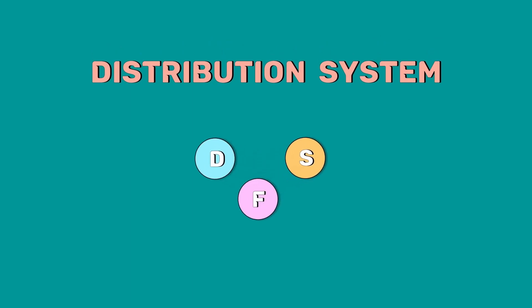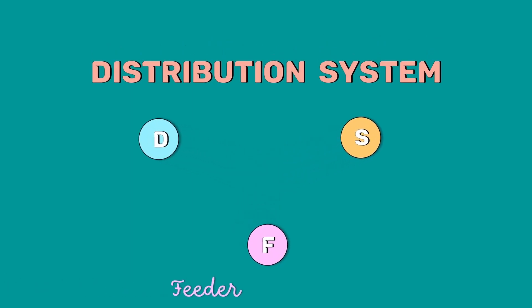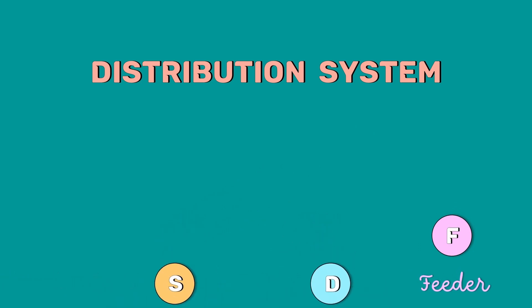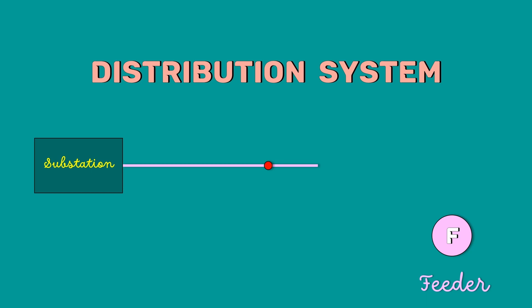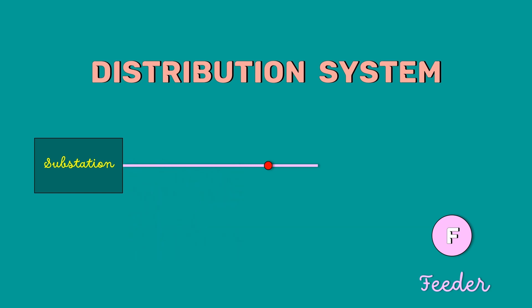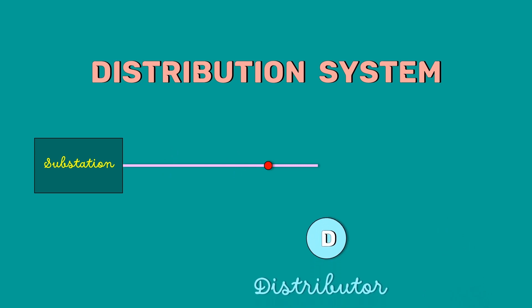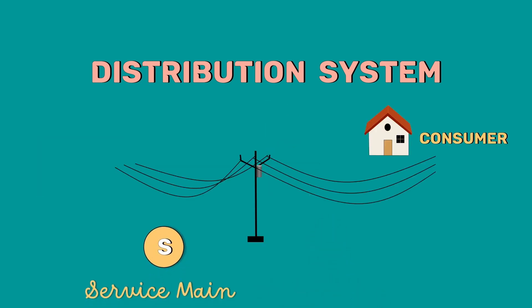The distribution system mainly consists of feeders, distributors, and the service main. A feeder is a conductor which connects the substation to the area where the power is to be distributed. Generally, no tappings are taken from the feeder so that the current in it remains the same throughout. A distributor is a conductor from which tappings are taken for supply to consumers. A service main is a small cable that connects the distributor to the consumer's terminal.